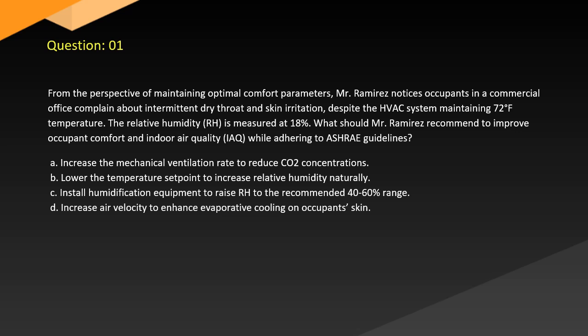Question 1. From the perspective of maintaining optimal comfort parameters, Mr. Ramirez notices occupants in a commercial office complain about intermittent dry throat and skin irritation, despite the HVAC system maintaining 72°F temperature. The relative humidity (RH) is measured at 18%. What should Mr. Ramirez recommend to improve occupant comfort and indoor air quality (IAQ) while adhering to ASHRAE guidelines?